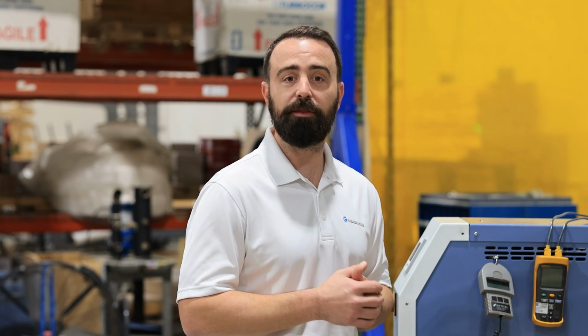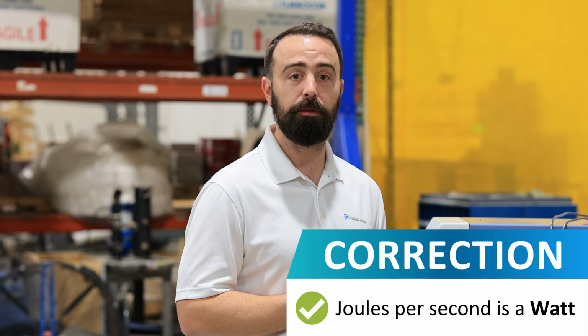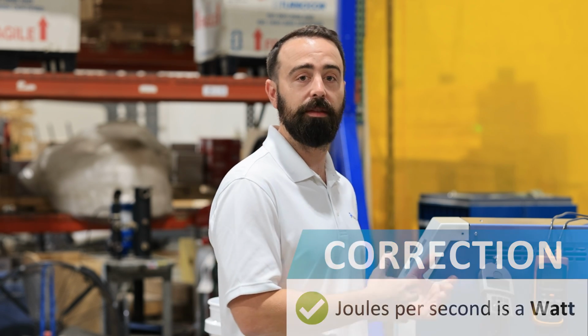Then we use the specific heat of water and the delta T that we've measured, and that allows us to calculate that Q, which is the energy transfer. We put it all over a time factor to give us a rate. And that's what a cooling capacity is. It's a rate. It's BTUs per hour or joules per second, which is a kilowatt. And so that allows us to calculate exactly what the real-world cooling requirement is.